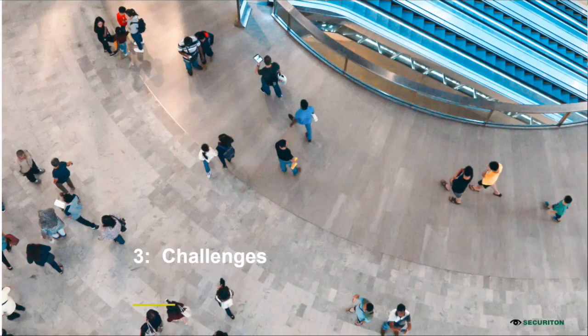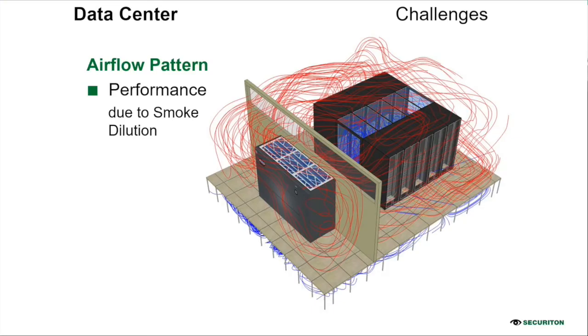Now we will talk about a few challenges due to the complex environment in a data center, and local norms also have an influence. There are a lot of challenges in designing a proper detection system because of these reasons. In data centers, there is a lot of air turbulence. That is the main part which doesn't allow you to design a proper fire alarm or smoke detection system.